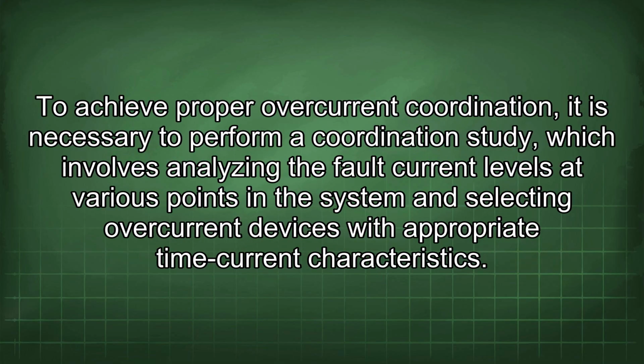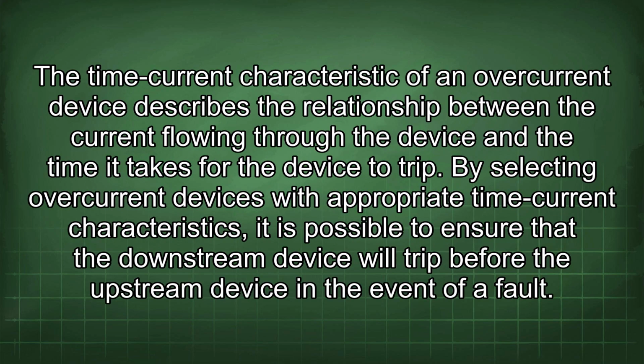To achieve proper overcurrent coordination, it is necessary to perform a coordination study, which involves analyzing the fault current levels at various points in the system and selecting overcurrent devices with appropriate time current characteristics. The time current characteristic of an overcurrent device describes the relationship between the current flowing through the device and the time it takes for the device to trip. By selecting overcurrent devices with appropriate time current characteristics, it is possible to ensure that the downstream device will trip before the upstream device in the event of a fault.